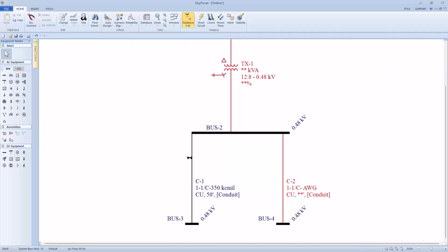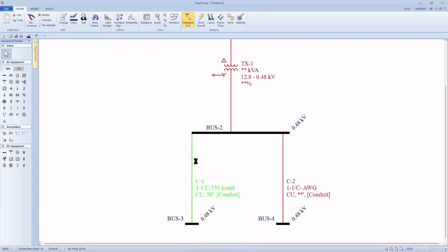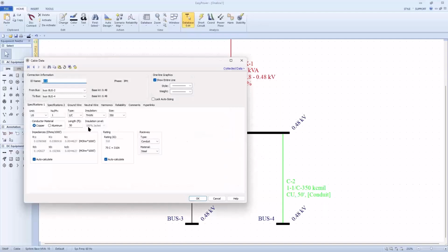He said, Jim, the second cable is the same as the first with a different length. So I'm going to right click on the first cable and copy, right click on the second cable and paste, and then open the dialog box. And sure enough, all that data came over. But instead of 50 feet, he said this cable was 1,000 feet long. So now I'm going to put 1,000 feet in there.